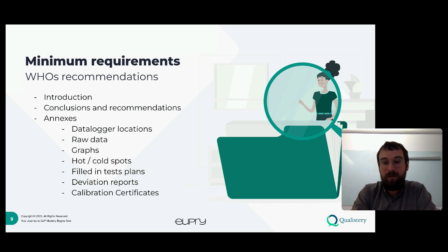If you perform regular reviews of the constant monitoring and the tendencies in it, and regular technical reviews of the HVAC systems, it's very rare that there's a high risk that you'll be non-compliant. That's not the same as saying you won't have a negative tendency in terms of staying within those acceptable ranges. But for larger warehouses, it takes rather large technical changes for you to be non-compliant. So again, rule of thumb: large changes or every 3 to 5 years. That's what we see at least.